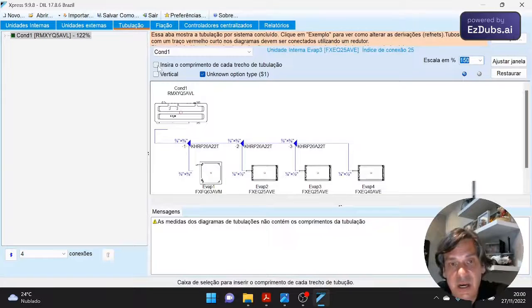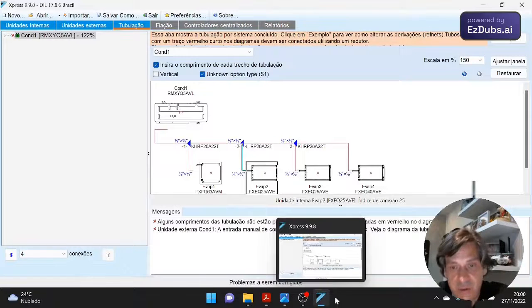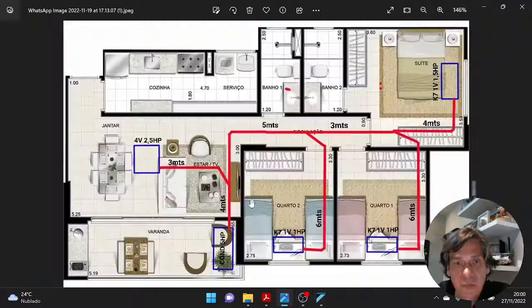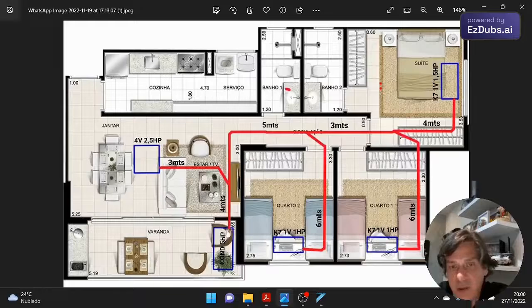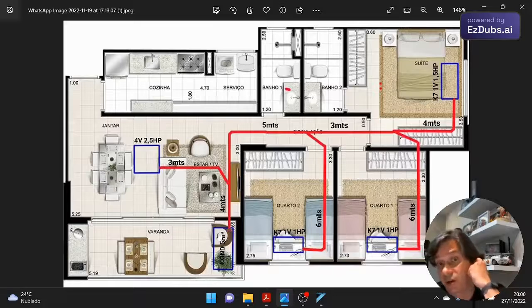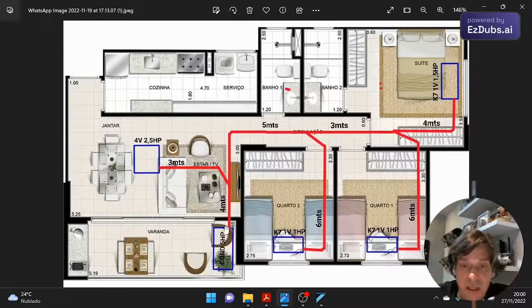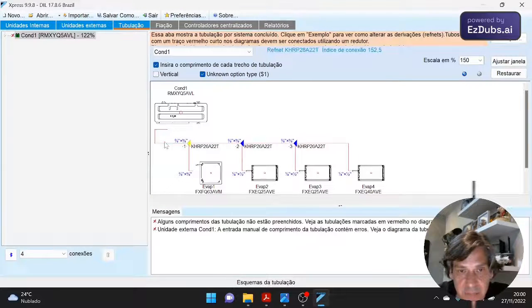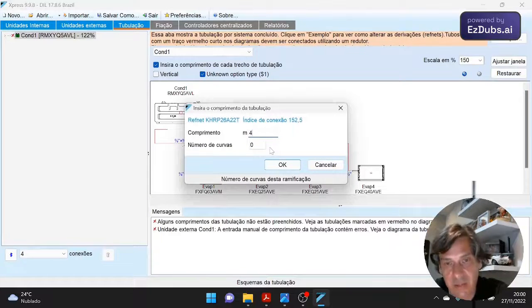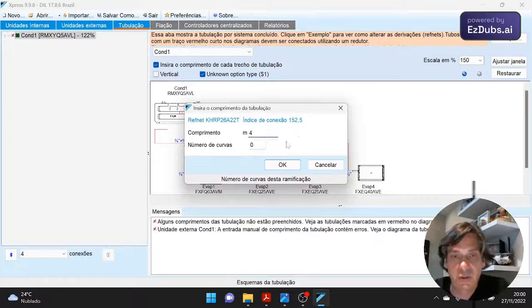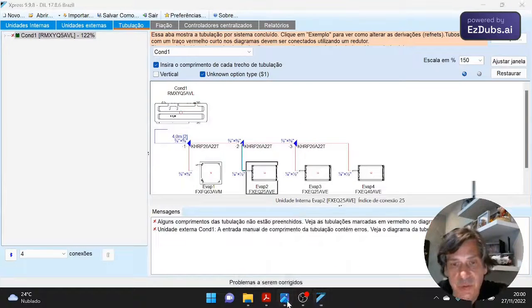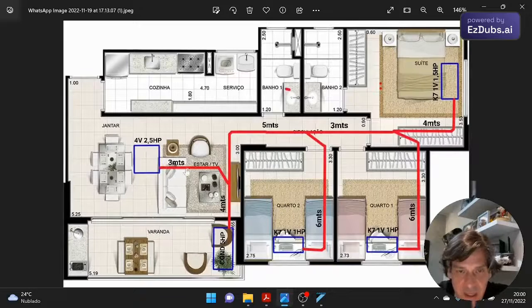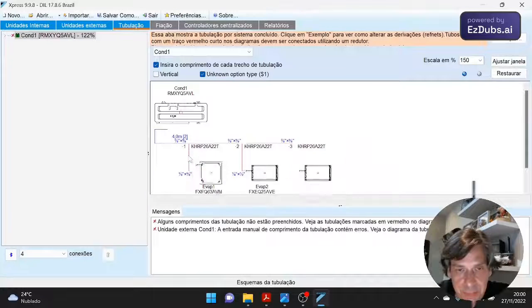Then I come here and click. Enter the length of each section of pipe. He already defined the piping, but I don't have the length. So I come here in my drawing. So my condenser is here. I'm going to walk 4 meters. Why 4 meters? Because it will travel 1 meter horizontally at the top, but the pipe comes out through the floor. Then it leaves the ground, rises 3 meters, and moves another 1 meter horizontally, 4 meters. Done. So we click here. I'm going to walk 4 meters as she left the ground, made a curve, reached the top, another curve, 2 curves. So let's move on to my second section of piping, which is this one from my cassette. So I'm going to walk 3 meters, and I'm going to make a turn. 3 meters, a turn.